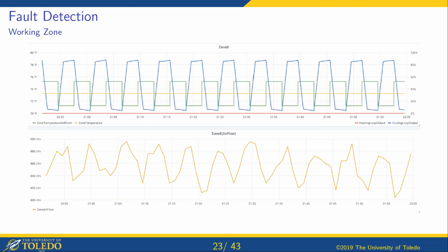The normal building automation system, while it's able to keep trends, doesn't normally have a database with trend information for every point within the system, but we do. So here what you're looking at, we were sending a test signal to every zone on our buildings simultaneously, pulling up the set point by 2 degrees and then setting it down 2 degrees from where it was already sitting every 3 minutes, and watching how the various systems responded and how that signal propagated through from beginning to end.